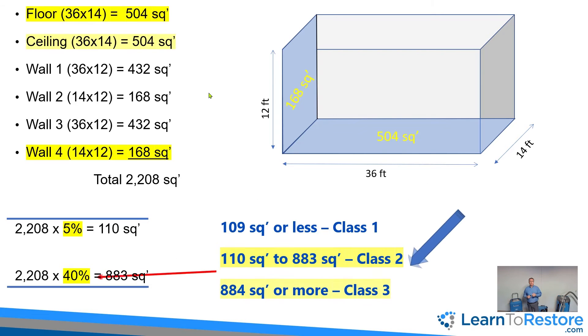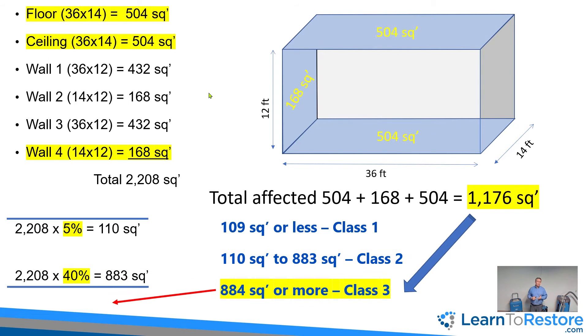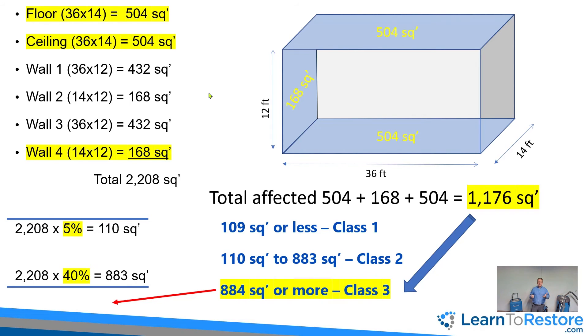If we add the ceiling being wet as well, now we have the floor, the ceiling, and wall number four for a total of 1,176 square feet. Since that's more than the 40% threshold of 883 square feet, that would be a class three loss. So the calculation is pretty simple: do your moisture mapping, figure out the overall surface area in your drying chamber, determine the percentage of what's wet, and that gives you class one, two, or three.